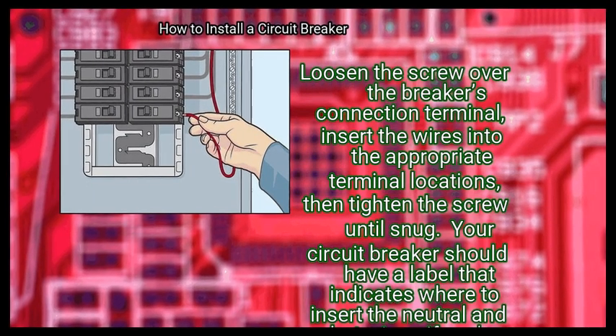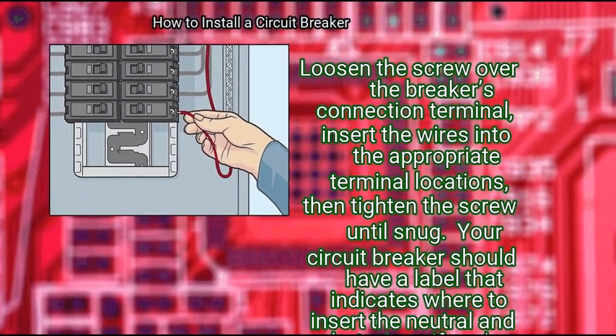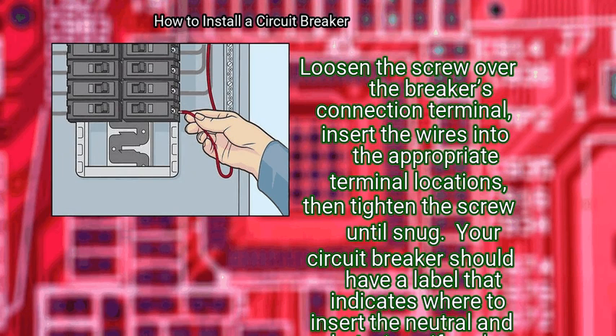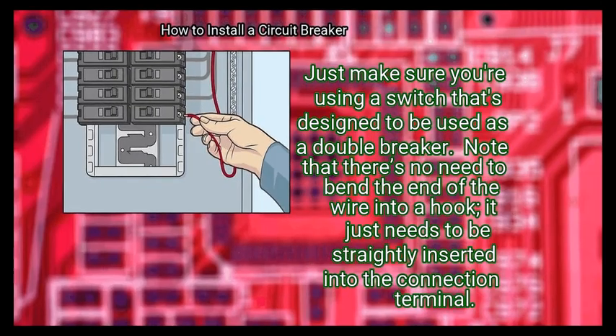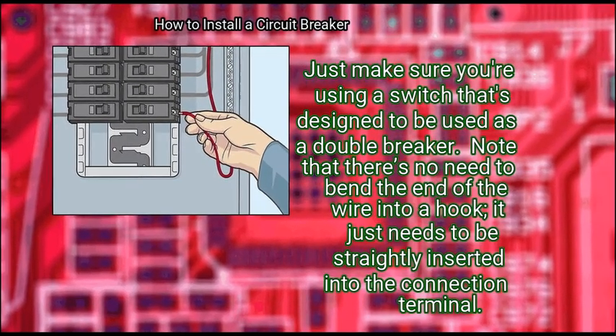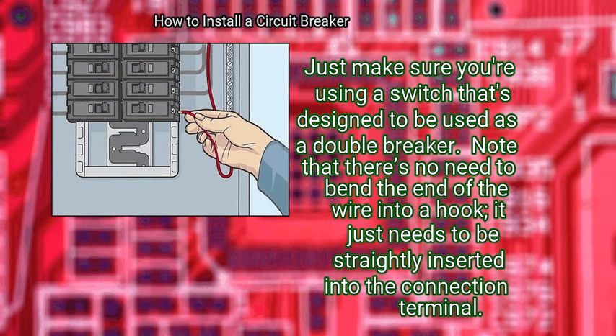Loosen the screw over the breaker's connection terminal. Insert the wires into the appropriate terminal locations. Then tighten the screw until snug. Your circuit breaker should have a label that indicates where to insert the neutral and hot wires. If you are installing a double pole breaker, you'll connect it to both the black and red hot wires. Just make sure you're using a switch that's designed to be used as a double breaker. Note that there's no need to bend the end of the wire into a hook. It just needs to be straightly inserted into the connection terminal.